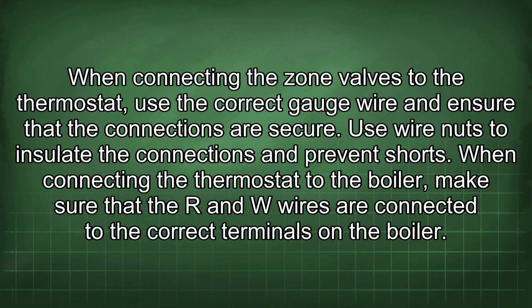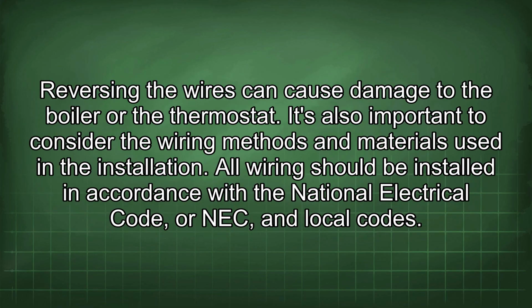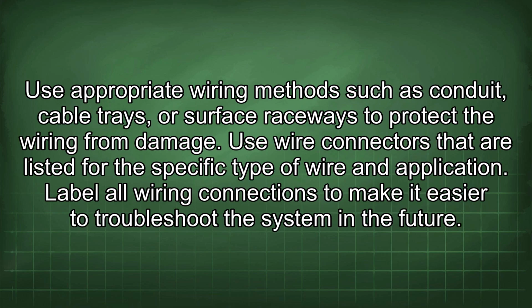When connecting the zone valves to the thermostat, use the correct gauge wire and ensure that the connections are secure. Use wire nuts to insulate the connections and prevent shorts. When connecting the thermostat to the boiler, make sure that the R and W wires are connected to the correct terminals on the boiler. Reversing the wires can cause damage to the boiler or the thermostat. It's also important to consider the wiring methods and materials used in the installation. All wiring should be installed in accordance with the National Electrical Code, or NEC, and local codes. Use appropriate wiring methods such as conduit, cable trays, or surface raceways to protect the wiring from damage.